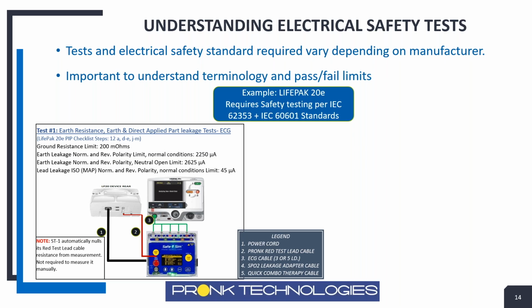So it's not NFPA, and it's not just a single standard. They're doing kind of a combination of standards. They're using the 62353 standard for some tests, and for some other tests, they want you to use the 60601 standard. So it's important to understand this in the service manual because you have to make sure you're testing accordingly. And this is a little busy, but this is an example of some of the tests. So they want you to do a couple of different tests.